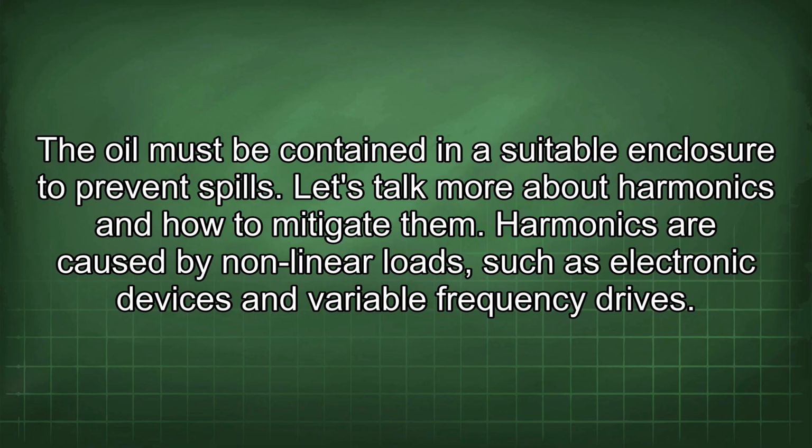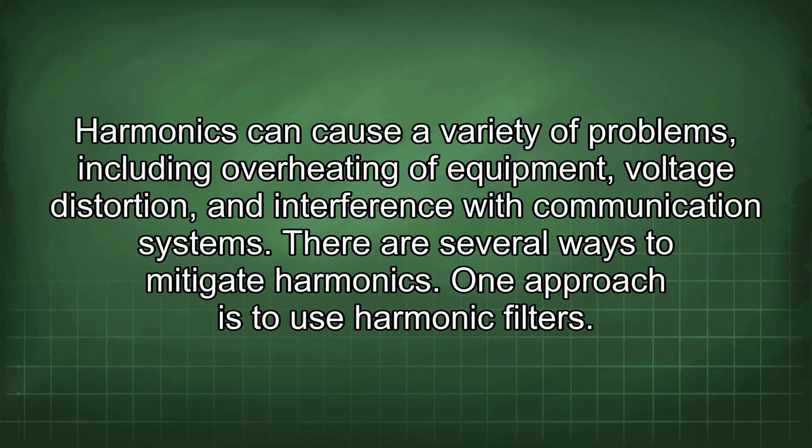Let's talk more about harmonics and how to mitigate them. Harmonics are caused by nonlinear loads, such as electronic devices and variable frequency drives. Harmonics can cause a variety of problems, including overheating of equipment, voltage distortion, and interference with communication systems. There are several ways to mitigate harmonics.